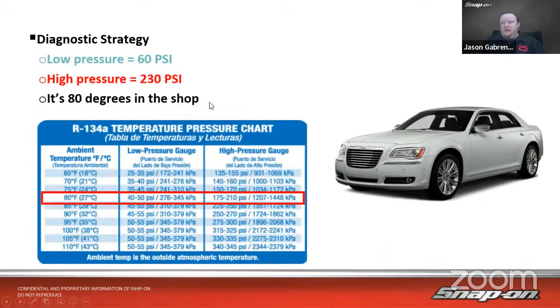On this temperature chart for this vehicle, if the ambient temperature is 80 degrees, the low pressure gauge should be 40 to 50 psi. The high pressure gauge should be 175 to 210 psi. So 60 psi is 10 more than we need there. And then 210 to 230, that's 20 more right there. So we definitely have over pressure in this system.